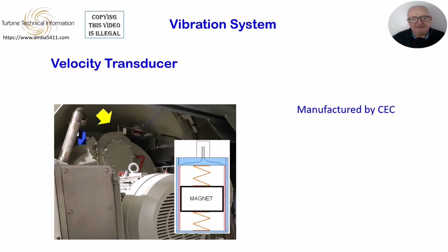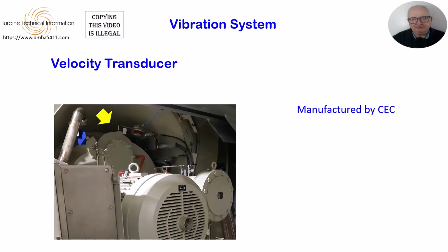It has an internal magnet suspended by two springs with a coil attached to the case. The output signal results from relative movement between the magnet and coil when the case vibrates. There are different sensitivities available in this model. Solar normally uses one with 145 millivolts per inch per second.